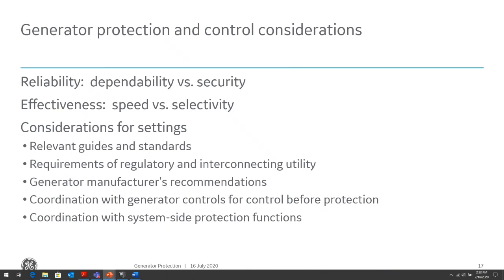So when we talk about reliability, there's a delicate balance between dependability versus security, where we want it to trip for faults, and obviously we don't want it to trip for non-fault situations. And then how effective is that protection system: how fast does it trip for faults within its zone of protection, or how fast does it trip for faults outside of its zone of protection? How does it coordinate for faults outside of its zone of protection, and selectivity to only trip for faults within its zone of protection, unless for faults outside of its zone the protection elements associated with those systems are not operating properly. Then we want to trip the generator, protect the generator from outside faults, outside zone faults.